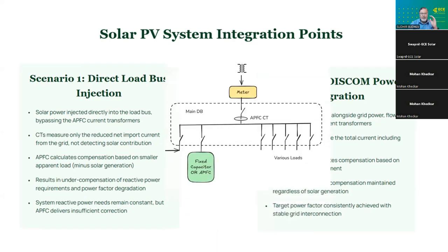So let's first see, in case you are an LT consumer, then we'll have a transformer, then the meter, and then the LT bus where various loads will be connected. We'll also have some fixed capacitors, or maybe APFC, or a combination of both. And if you are HT, then probably the meter will be before the transformer. This is a normal scenario. Now, when you want to install solar, the solar integrator will come, inspect the site, and say, okay sir, you have one breaker, 800 amps, 1000 amps, whatever, that is free, extra. I can use this, and you can save on the money. So we will install and inject power here.